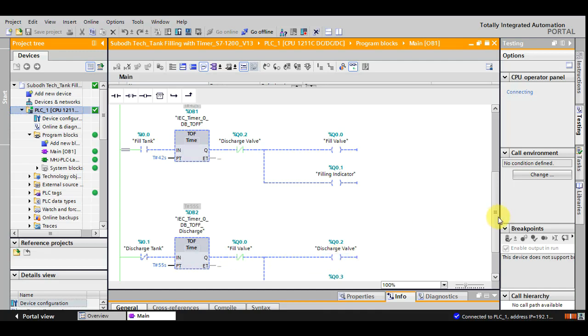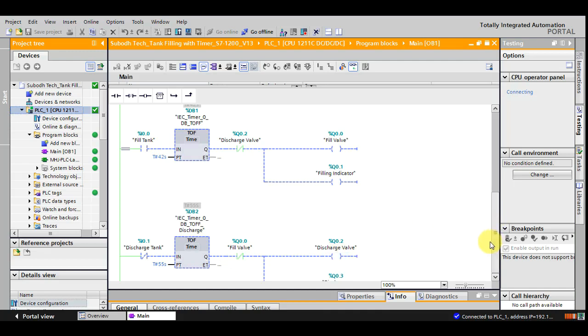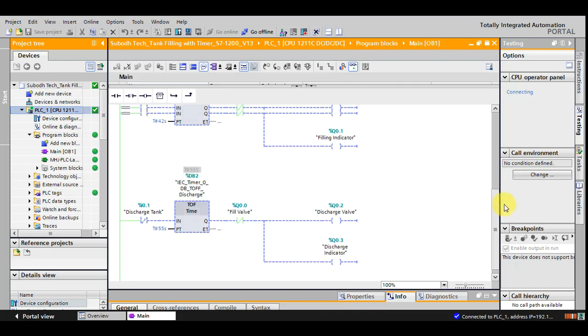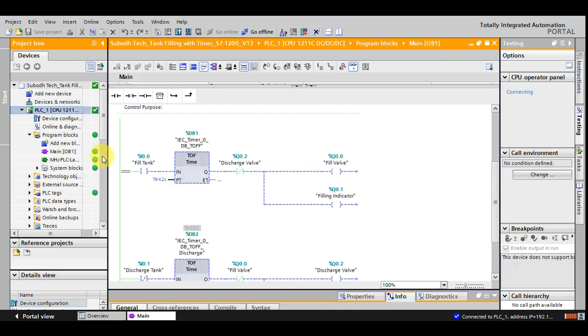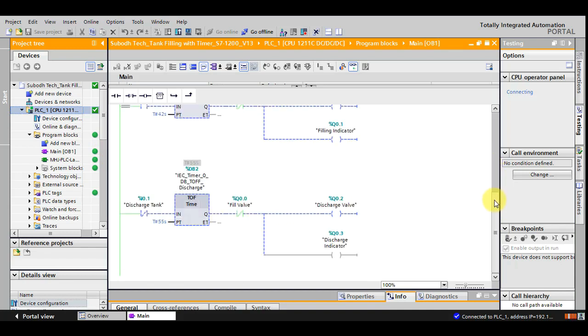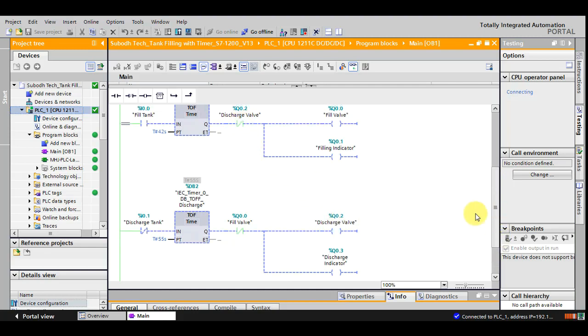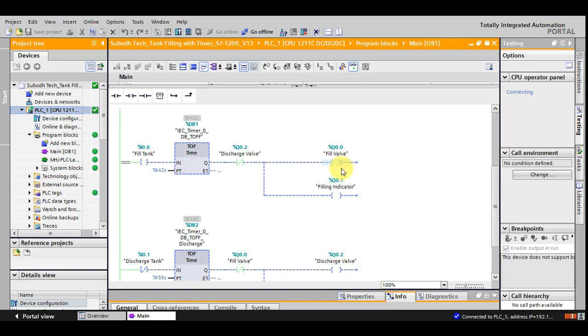Same condition, if someone has pressed discharge push button and the fill push button is not generating any output, then in that case, after pressing the discharge push button, if someone is pressing the fill push button, then this output, the normally closed contact of this output that I have kept here, it will not allow to generate the output for the fill valve. So you can avoid that particular instance.